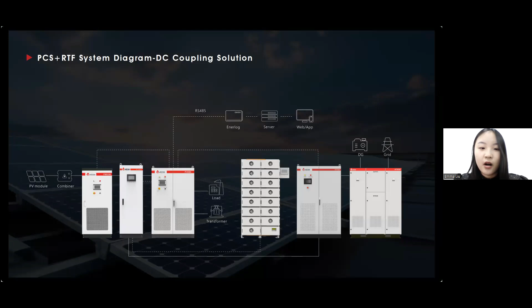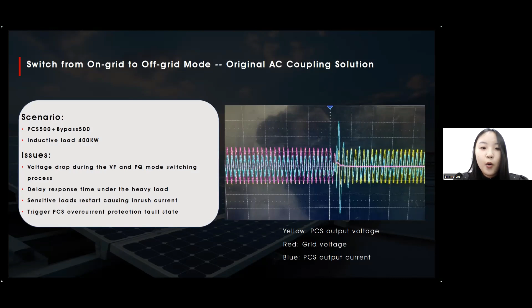First one, when the grid fails, PCS will switch from on-grid to off-grid mode, but the inductive load percentage reaches 80%. In this case, check out the pink line, which is the voltage line. It dropped during the switching process, right? And caused inrush current, which triggered the PCS over current protection fault state.